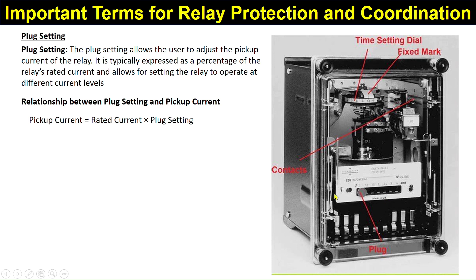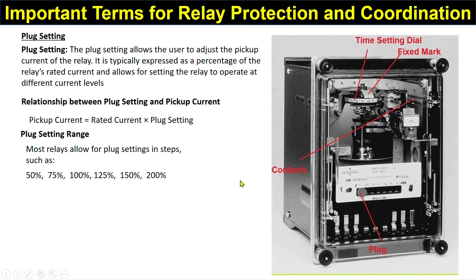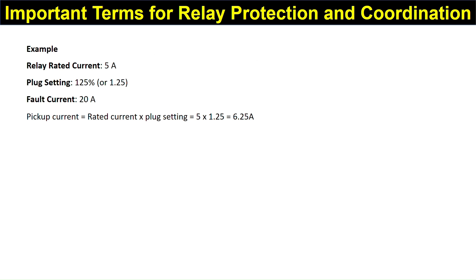Plug setting range: most relays allow plug settings in steps such as 50%, 75%, 100%, 125%, 150%, and 200%. For example, if the relay rated current is 5 A and plug setting is 125%, the pickup current is 5 × 1.25 = 6.25 A. Since the fault current of 20 A exceeds 6.25 A, the relay gets activated.